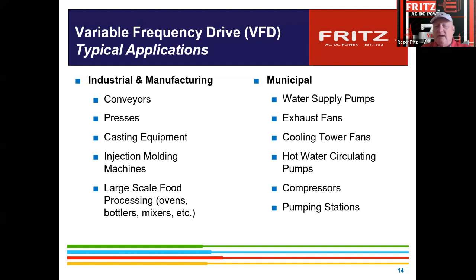chilling water. We did some processing machines where we put about 60 or 70 drives on molding machines for an optical lens company, and we were able to take 300 tons of chiller off the roof, which they were using to cool the hydraulic oil chillers, and also cool down the building. A lot of compressors, both reciprocating, and both air and refrigeration compressors, balancing that out.